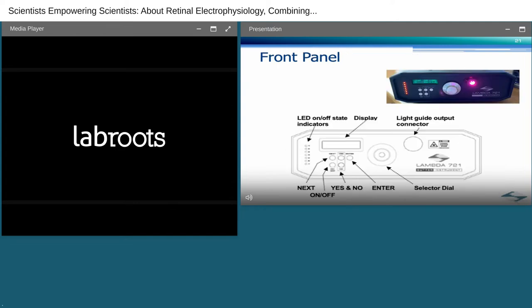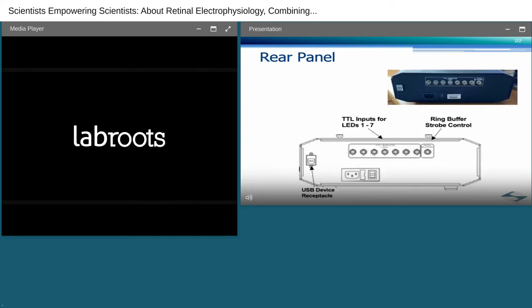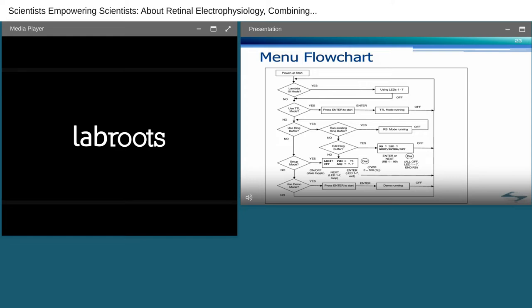Loosen the lock down screw and slide the light guide in and out until the circle on the wall has sharp edges and is uniform, as shown in these images. Tighten the lock down screw, power off the 721 and install the adapter onto the microscope. Now that we have the hardware properly connected, let's review the front and rear panel controls. There are only a few controls that you will need to get acquainted with on the front panel. On the left hand side, we have the LED on-off state indicators, which are extremely useful, especially when testing. To the right of that is a display which shows the menu selections and device status, followed by controls for traversing and selecting the various menu choices located on the right and below the display. Finally, the light output port.